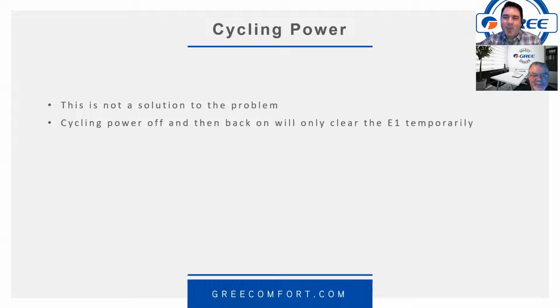Yeah. Sometimes, I believe it goes through, not the E1, because the E1's a safety, but a lot of the codes, it'll go through a series of 5 to 7 times of attempting and seeing if there is a code that comes up before it actually locks out. So it could be occurring at the moment. It's just not locking out yet because it wants to continue providing cooling or heating. Yeah.